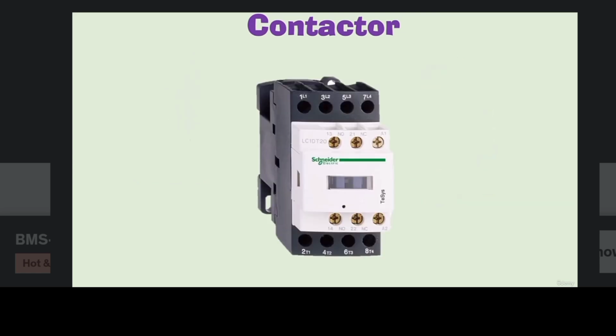The contactor shown here is a 4-pole contactor where we can connect three-phase line voltages along with the neutral. Power supply line voltage is applied on the upper terminals and the load is connected on the lower terminals. Control voltage is applied on the A1 and A2 terminals, same as a relay. Control voltage can be either DC or AC depending on the rating of the contactor. You can find the rated control voltage on the contactor nameplate or in the datasheet of the contactor.